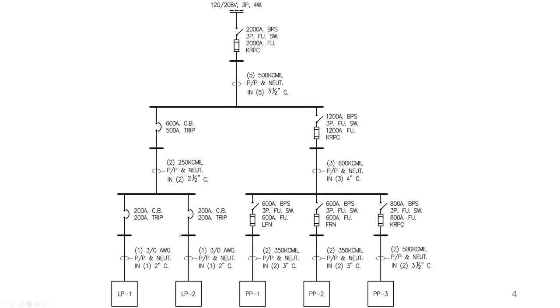If I have, for example, this 800 amp device that is supposed to be the panel board, what you may want to think, and of course, there's no way I'm going to have selective coordination between this 800 upstream to this 1200. So I may want to take this 800 out and feed it directly out of this bus. But you are redesigning the job, and the electrical contractor is not going to like that in the field because he's going to end up spending more money. The owner is also trying to save money, of course. So you have to look at those things.